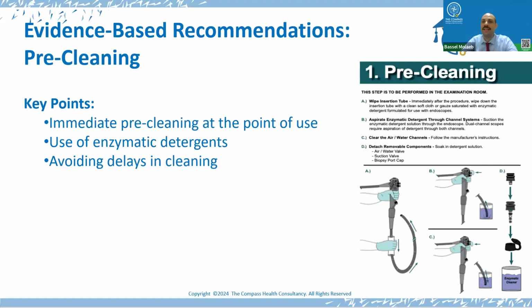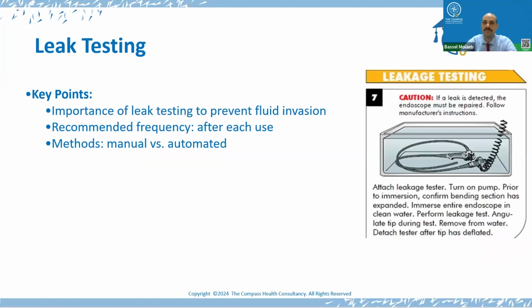Starting with pre-cleaning, this must be done in the procedure room immediately after removal of the insertion tube from the patient and prior to disconnecting the endoscope from the power source. It should be performed at the point of use, before bioburden has an opportunity to dry and before complete decontamination, using the enzymatic detergent. Pre-cleaning of each device should be based on the IFUs. Keep this in mind. Leak testing is the next step.